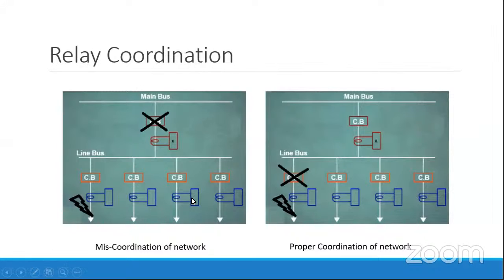So this leads to the blackout condition to the other outgoing feeders. The power is interrupted to other outgoing feeders also. So this is not a proper power supply scheme or protection scheme.